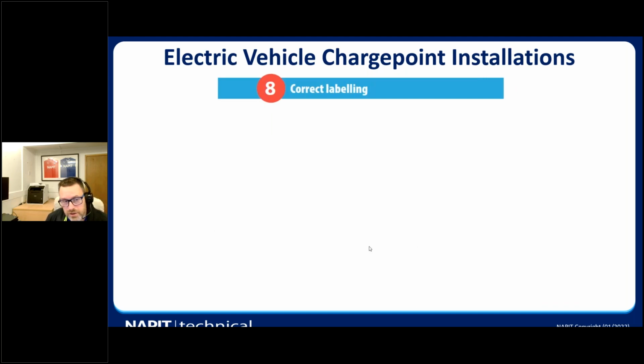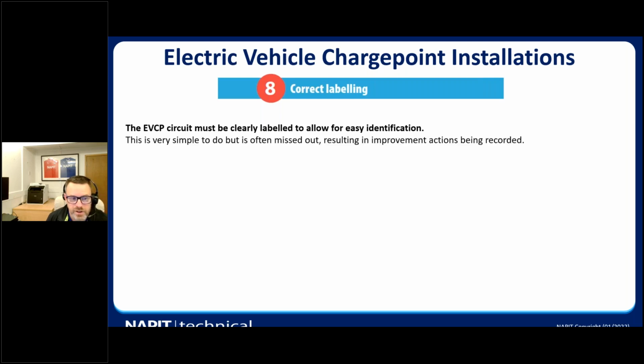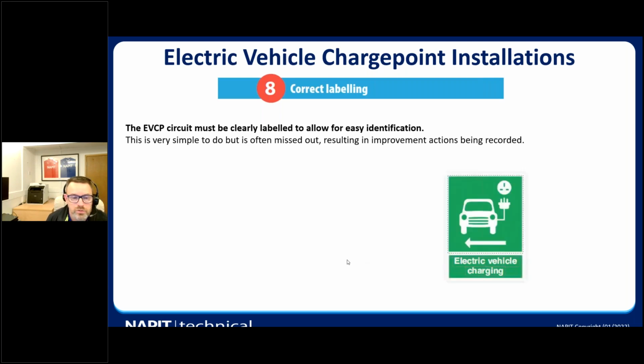Correct labelling is number 8. An EV charge point must be clearly labelled to allow easy identification of the circuit, of the equipment, and for safe isolation and safe operation of it. It is simple to miss out these labels, but it will result in an improvement action being recorded on any audit and any assessment. So correct labelling of EV charge points must be carried out.